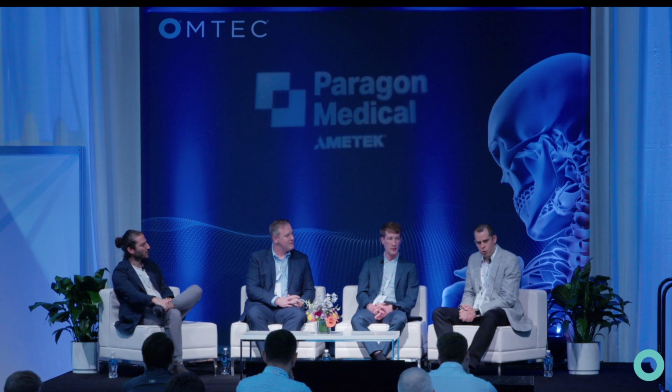What about you, Craig, especially with the slurry and the way that works with the binding? Yeah, I think a robust cleaning validation would be needed, especially for a porous form. So prior to the sintering that I had described, after the green body, there's an airbrush step that removes any loose ends or components that haven't been fully cured as part of the blue light process. We have a lot of experience dealing with particulate when we're performing traditional blasting and coating. We have a few FDA reviewers that we're in conversation with right now about the matter. So it's definitely a red flag. But I would say performing a robust bioburden, cytotoxicity testing, and SEM with EDAX is also a really valuable tool.